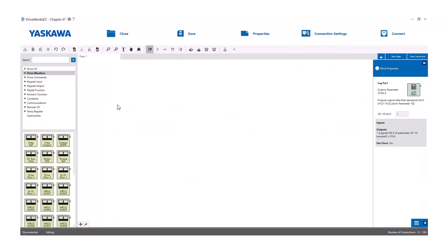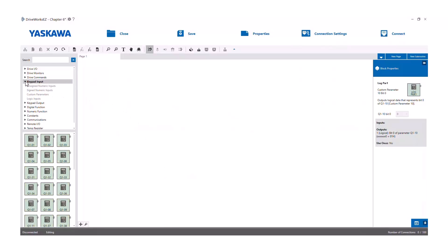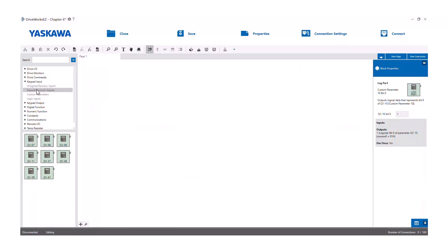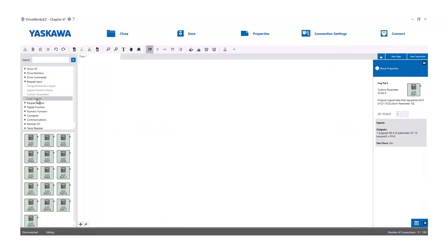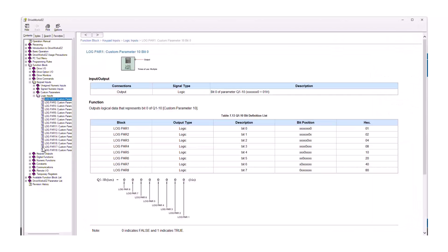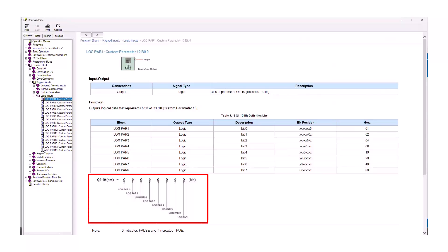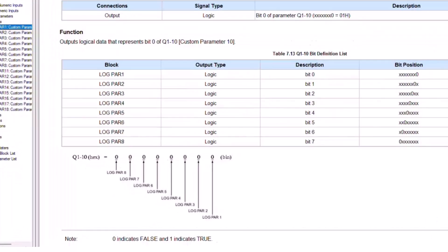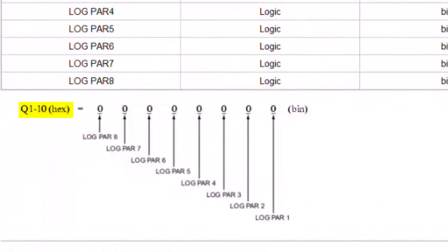Jumping over a couple of tabs, we see that there are keypad input blocks. These blocks allow the user to interface with the DriveWorks Easy program through the drive's keypad. The numerical output of this block is determined by the value entered by the user. The different blocks have different ranges, all of which are in percentage, and some keypad inputs are signed — either positive or negative — and some are unsigned values, depending on the block selected. Next to these keypad inputs are logical keypad inputs. These provide a logical output determined by the setting of parameter Q1-10, which can be changed by the user from the keypad or in the DriveWorks Easy interface. Note that Q1-10's setting is a hexadecimal value, not a binary one.